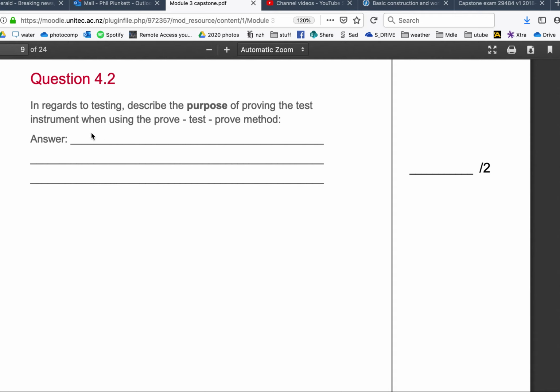That is to get a reading on your meter so you know your meter's working. And then at the end, when you do it again, is to get another reading on your meter so you know your meter's working again, so it hasn't broken between these 2 points here. You haven't knocked the lead out or anything.